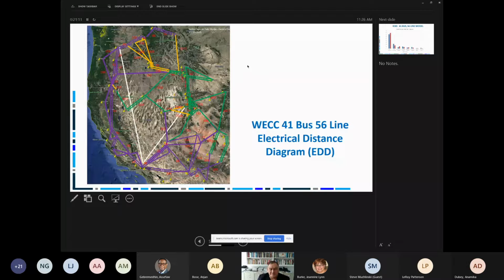We are seeing the phenomenon of inverter-based resources having a cascading effect. One gas turbine will trip offline, and the wind farms and solar farms in a 200-mile radius will see that voltage dip, and they will also decide to trip off. And NERC has been saying we've got to run the EMTP studies where we actually simulate the waveform. And what that requires is we come up with dramatically reduced model sizes.